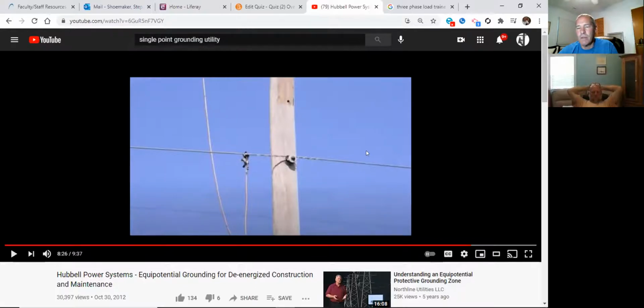Any guesses? Do you think the jumpers themselves have a rating as far as the amount of current that can flow through them? Yes, they do. All right. Remember, we're coming here with a cluster bar, then we're taking a jumper to the neutral. Then off the neutral, we're taking another jumper up to the phase. In some cases, the neutral conductor will not be able to carry the amount of fault current that the cable does. So they have a different method here.